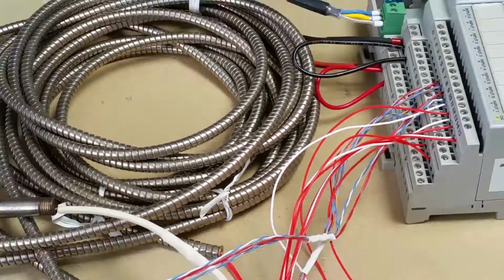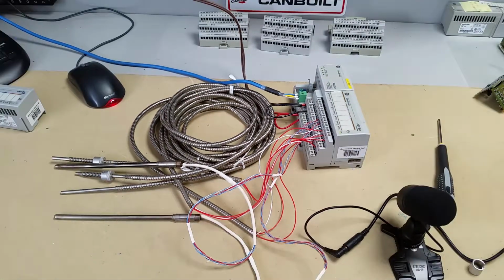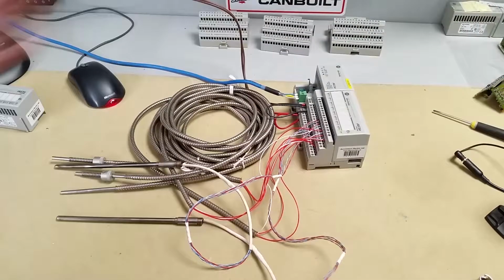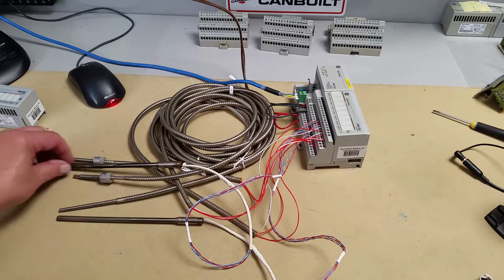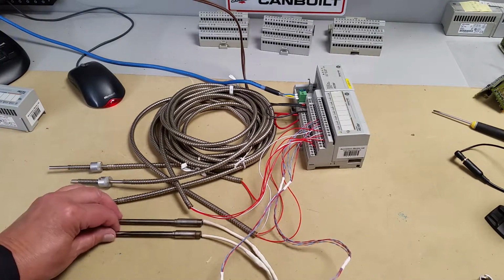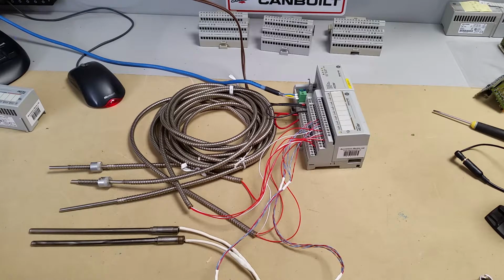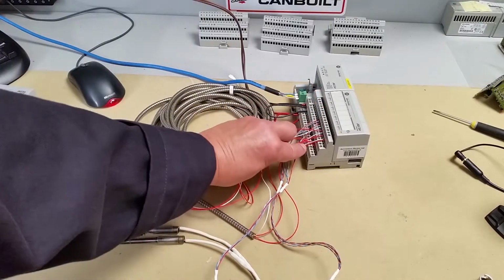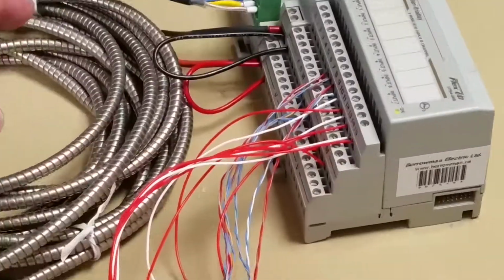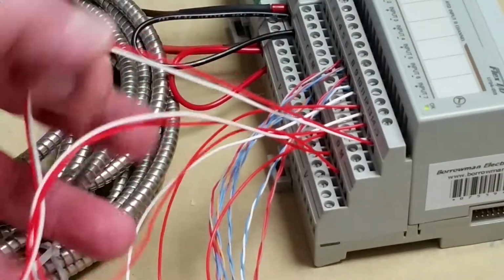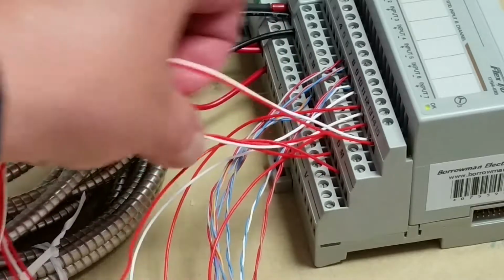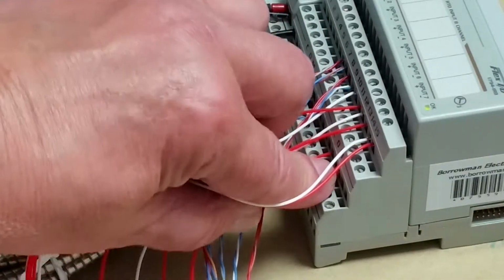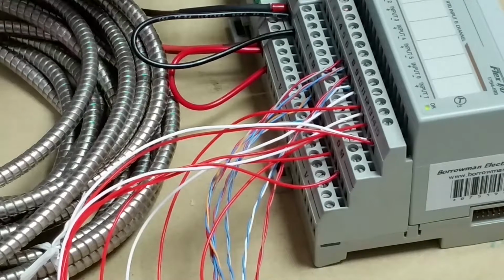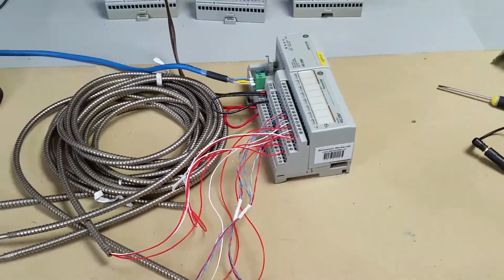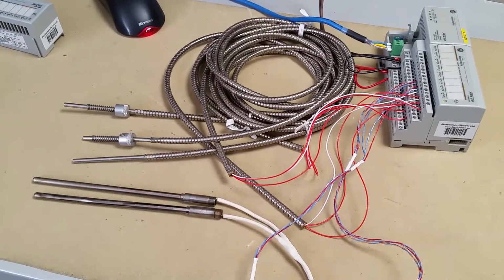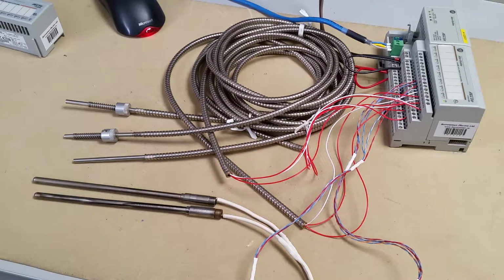And here we go. Back out a little bit. Now, like I say, I have, and I'll just move the microphone out of the way, what we have here is 5 RTDs. 3 of them match this way, 2 of them match that way. They're all 100 ohm platinum US. You wire them up here with, let's see if we can zoom in a little more, taking this one here, you use white, red, and then red goes on the appropriate terminal down below. So everything is wired the same, everything works the same, and you know that everything is good because you've got your temperature and it's on and off.